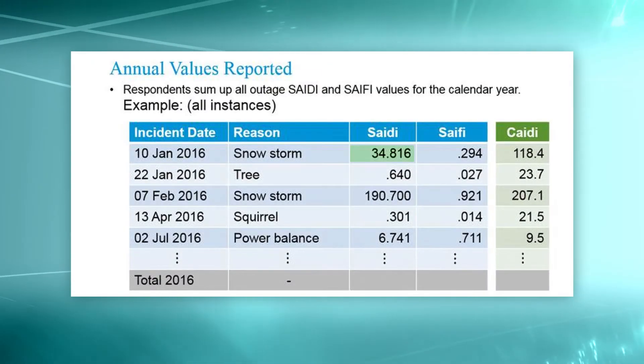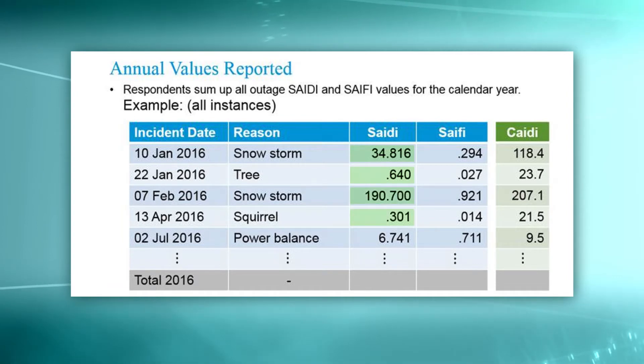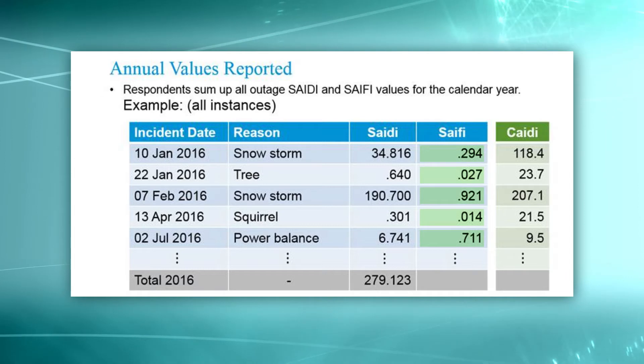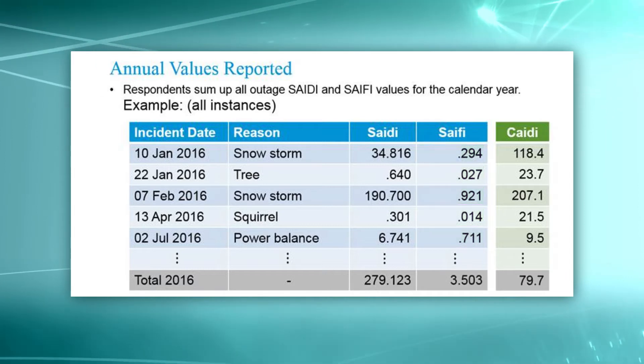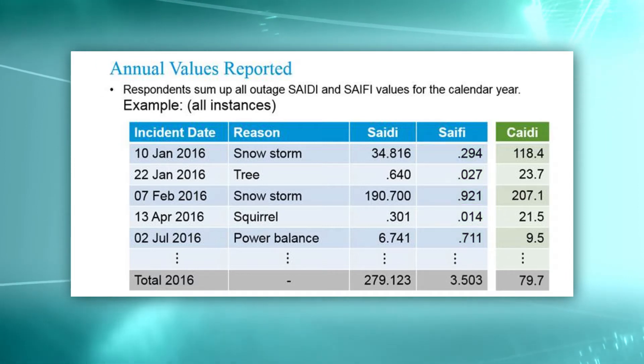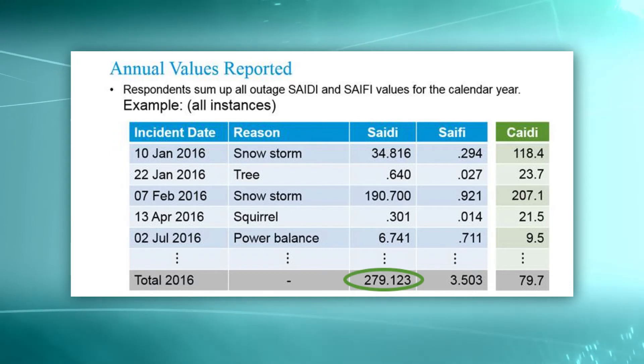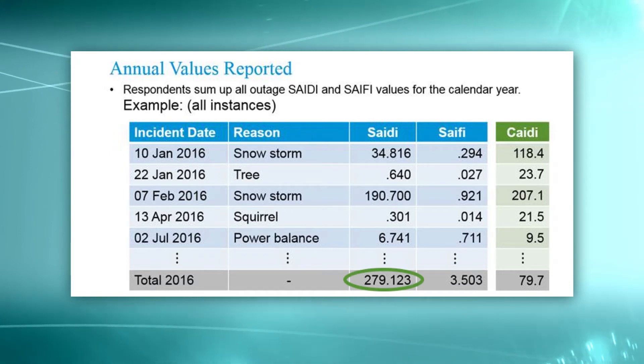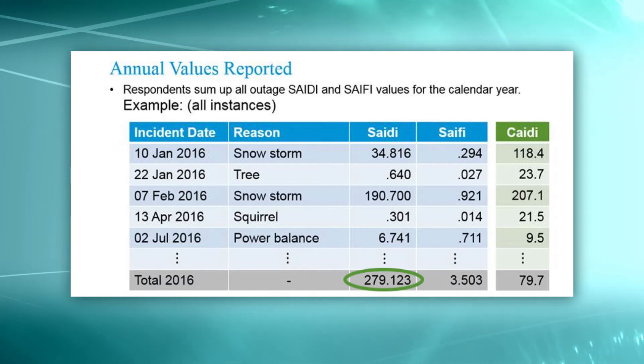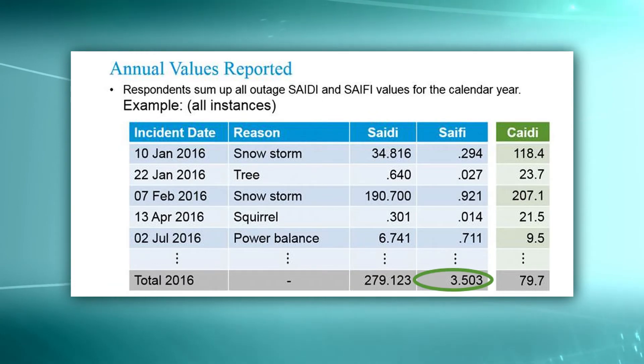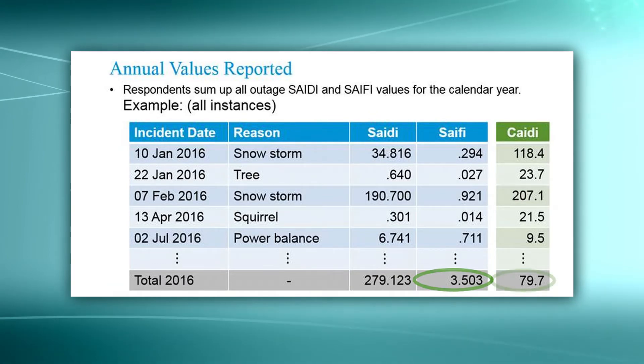At the end of the year, add all the SAIDI values together to get the yearly SAIDI. Do the same for SAIFI. In this example, you can see that the average person on the grid lost power for 279 minutes total — about four hours — for the year 2016, in 3.5 outages. The average duration of each outage was 80 minutes.